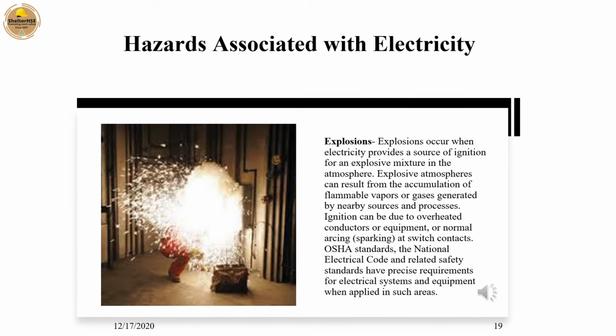Explosions occur when electricity provides a source of ignition for an explosive mixture in the atmosphere. Explosive atmospheres can result from the accumulation of flammable vapors or gases generated by nearby sources and processes. The ignition can be due to overheated conductors or equipment, or normal arcing, sparking, at switch contacts. OSHA standards, the National Electrical Code, and related safety standards have precise requirements for electrical systems and equipment when applied in such areas.